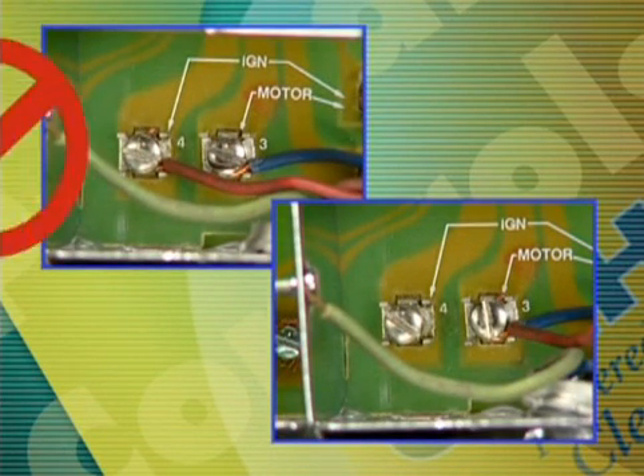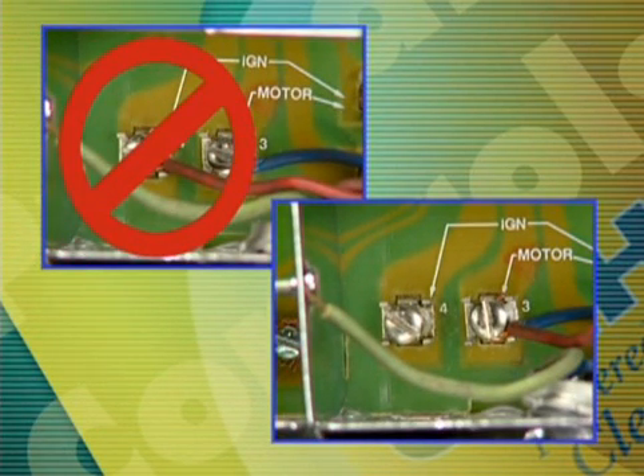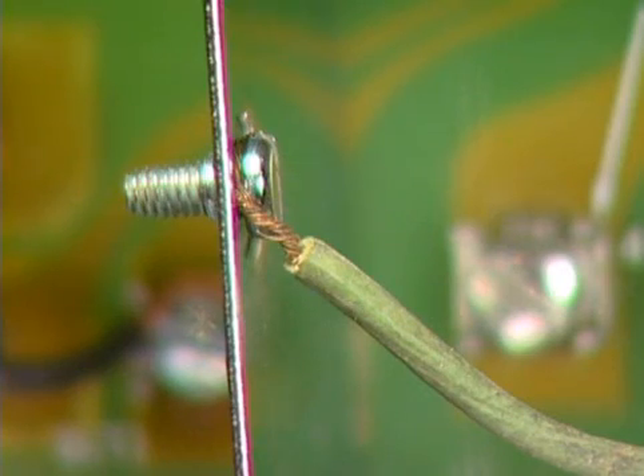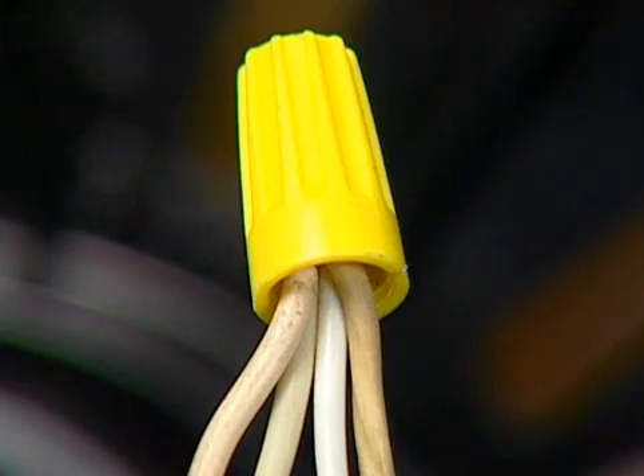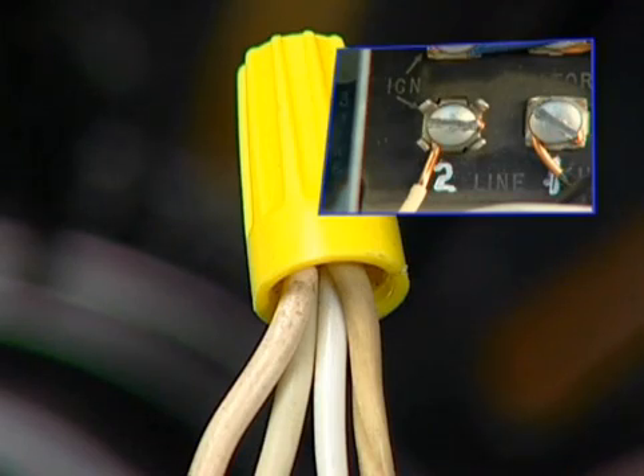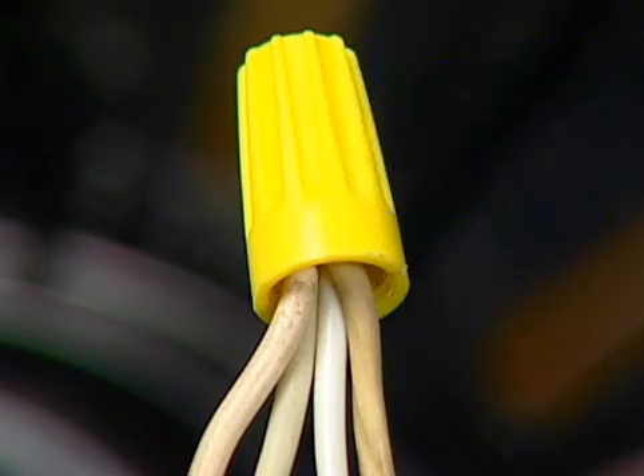For intermittent duty ignition, connect the transformer lead to terminal 3, along with the burner motor lead, leaving terminal 4 empty. If the control has a green terminal, it should be connected to ground. Remember, each component, the burner motor, transformer, and optional oil valve, has 2 wires. One wire from each connects to the neutral, terminal 2.